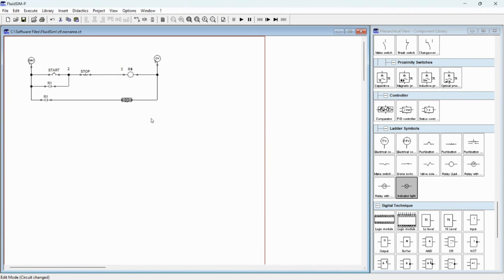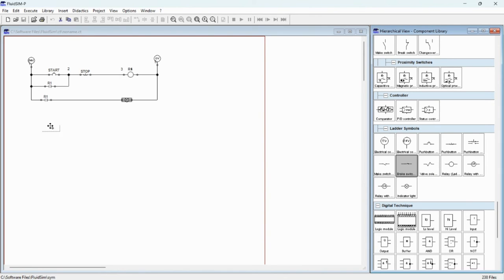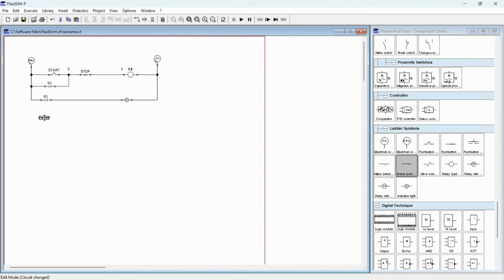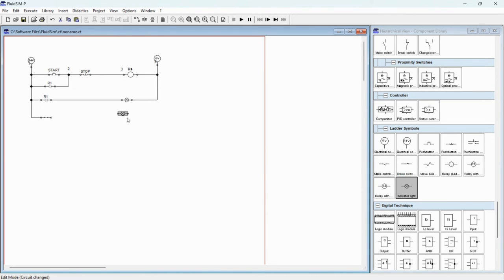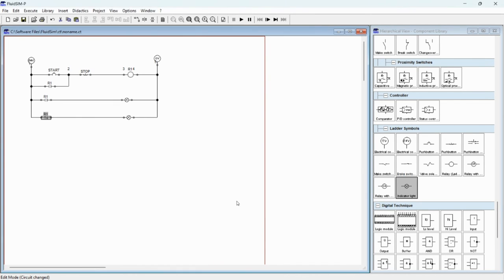Set the indicator to green so that you know the circuit is turned on. If the circuit is off — meaning if someone presses the stop button — then the red light will turn on. So we will use a normally closed contact, then connect an indicator light to this. Make it straight and connect here. Same as Relay R1 — you are using a normally closed contact from the relay.